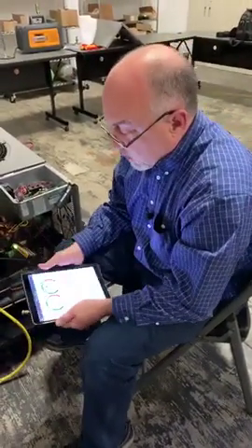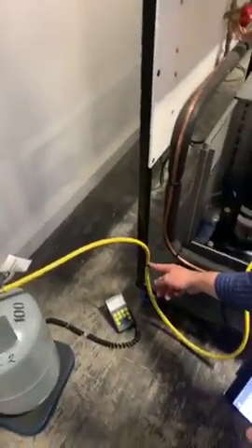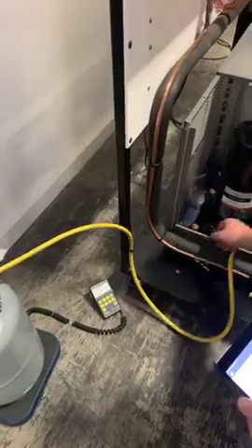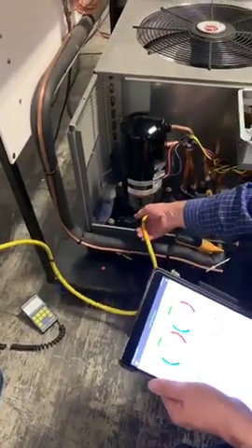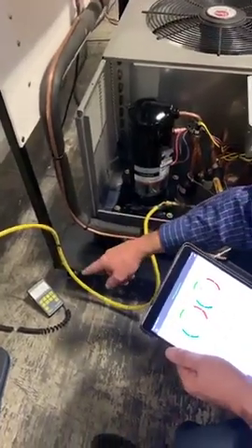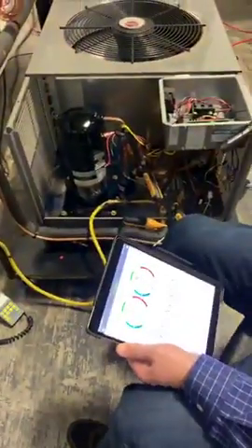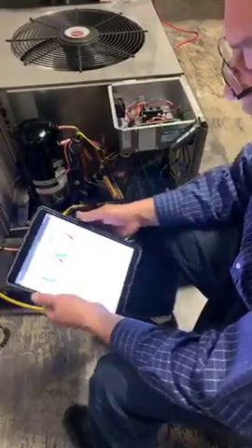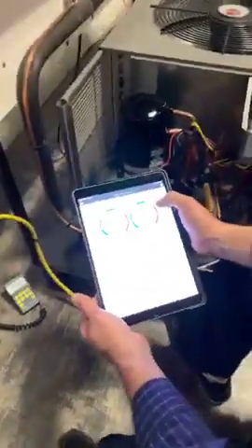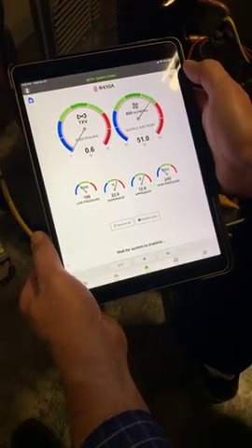A couple other things I want you to notice here. I tied my refrigerant hose off so that as I'm adding gas and moving this part of the hose, I'm not influencing my scale. And I zeroed out my scale. I have some recovered R410A in that tank, and I'm just adding it back into the low side of the system. Again, we're still waiting for that stabilization to occur. Our temp split's dropping into range right now, and things are moving.